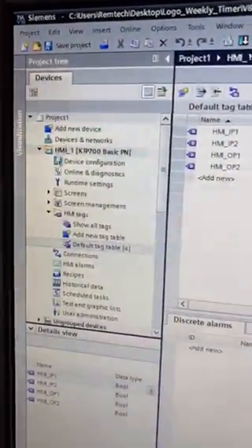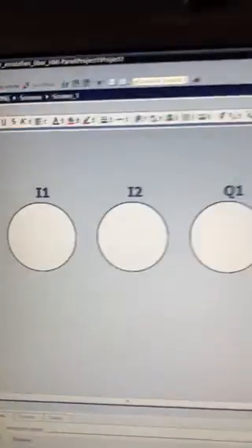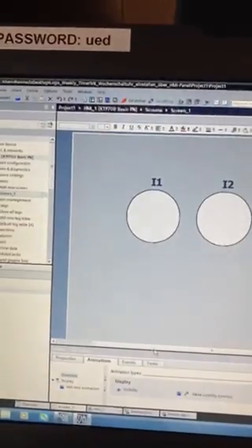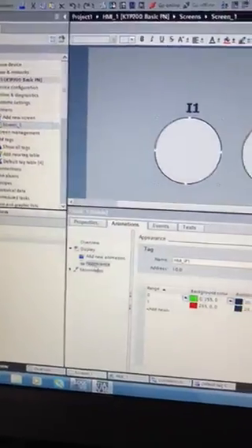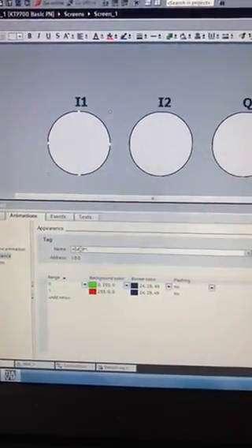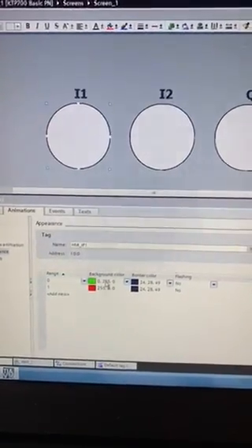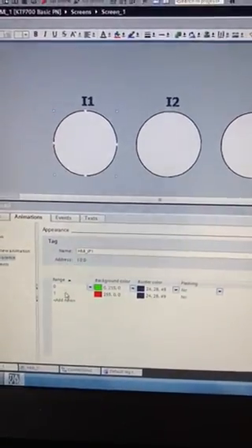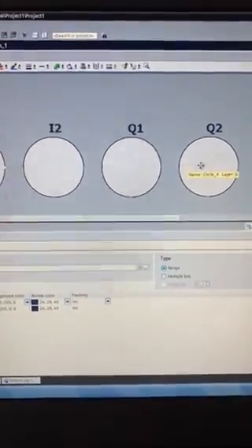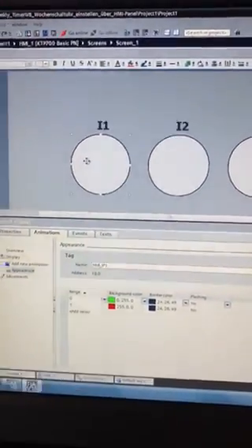Lastly, I've created a new screen with just some lights. What these lights do is each one is set up exactly the same. I've got a display appearance, and in there I've given my HMI tag input 1. If input 1 is 0 then green, and if input 1 is 1 then red. I've done that the same for all my lights there for my outputs as well. In theory, the lights are going to react opposite to the inputs because these are normally open.